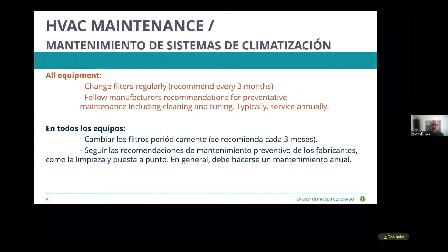There are some best practices, like changing filters regularly, every 3 months or so, and doing a clean and tune, or at least a clean and an inspection annually, of any type of HVAC equipment. We're talking water heaters, boilers, evaporative coolers, rooftop units, air conditioning. All of these have the ability, especially in Denver when we have air quality events, to get dirty quickly. It depends on where this equipment is located. If you have a furnace in a crawl space, I would assume those filters are getting dirty in an interval far less than 3 months, maybe every 1 to 2 months you're replacing those filters. Filters are cheap and they can really prolong the lifespan of your equipment.